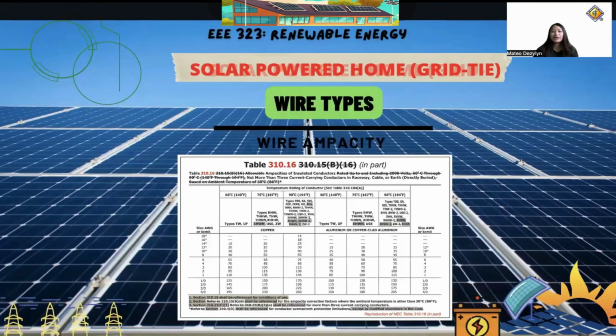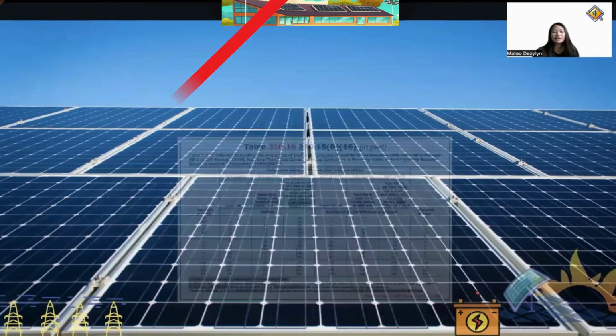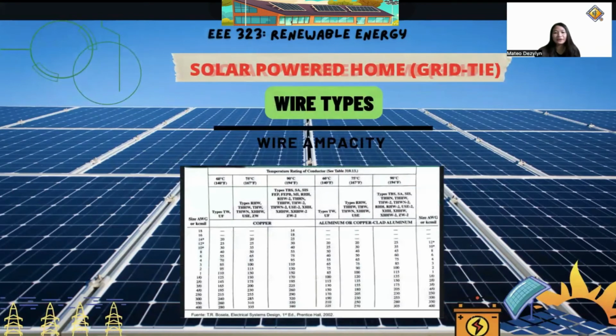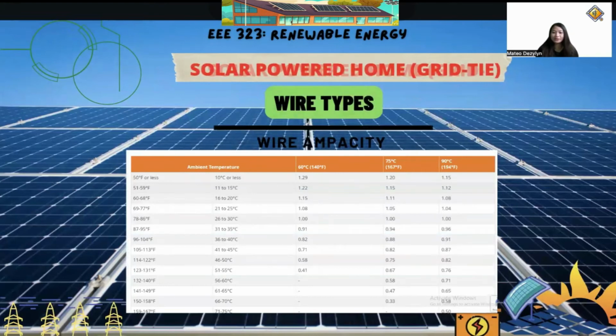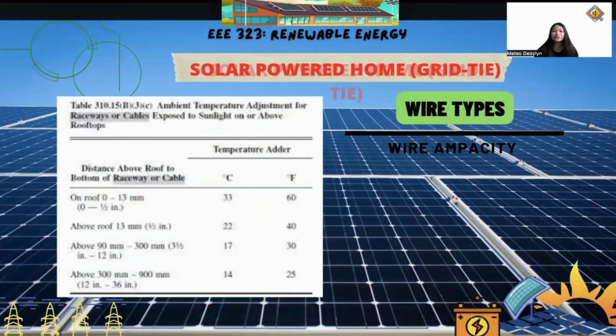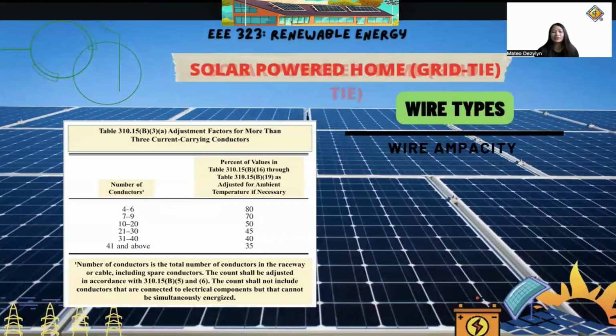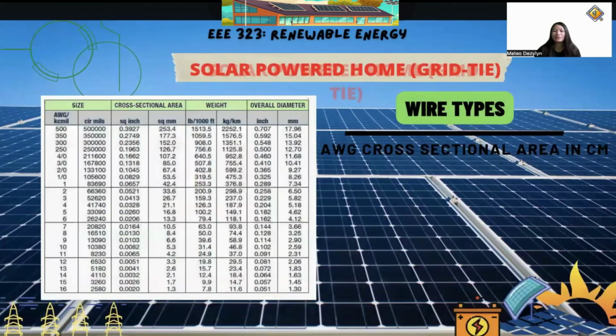Let's proceed to the tables that we can use in wire sizing. So this table is the ampacities of insulated conductors. Next is the magnified view, which starts at 14. This table is the correction due to ambient temperature. There is also an ambient temperature adjustment for raceways or cables exposed to sunlight on or above rooftops. Furthermore, we have adjustment factors for more than 3 current-carrying conductors. So, this is the American wire gauge cross-sectional area in centimeters.